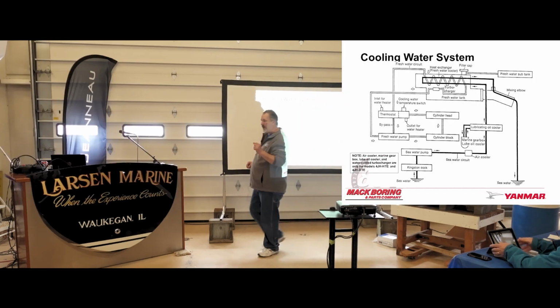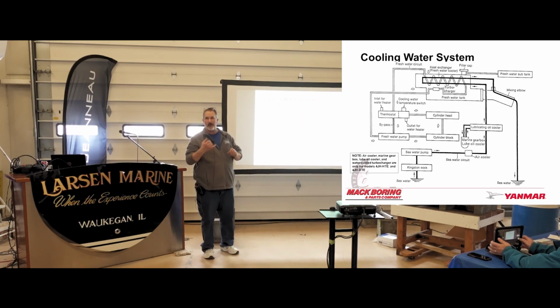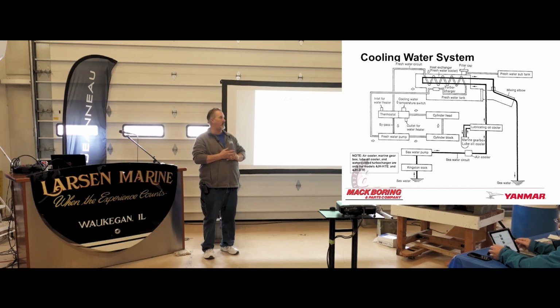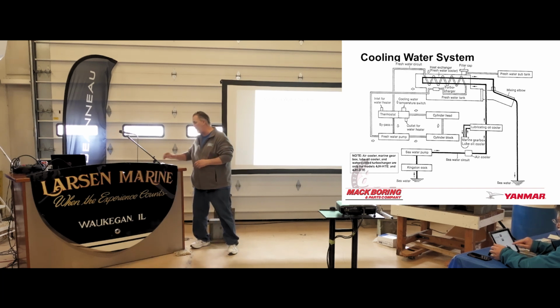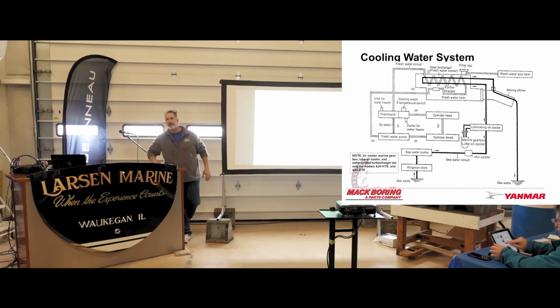With that mixing elbow, you now have hot exhaust gases and cold raw water going through it. You should have it inspected, not annually, but every six months, pull it off and check inside. Because you get calcium buildup, rust buildup, and several other things can happen that clog it up, putting excessive back pressure on the engine so it won't perform the way it's designed.